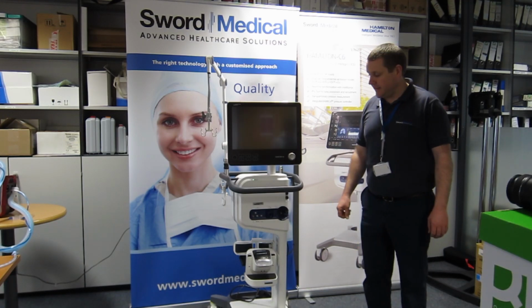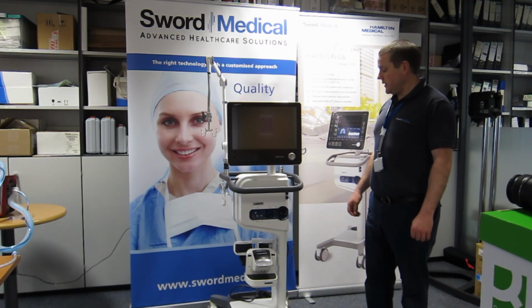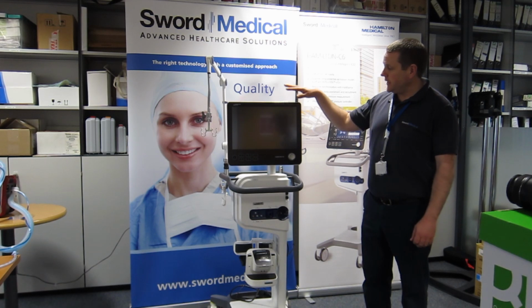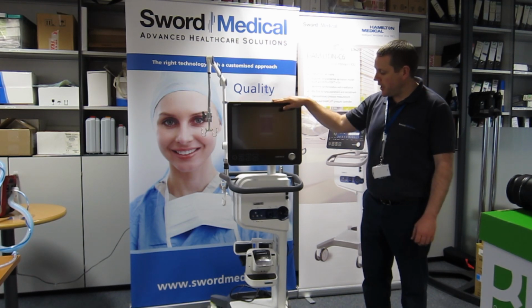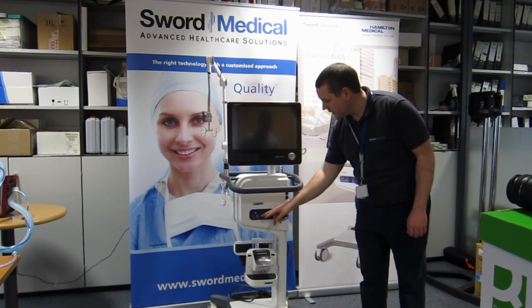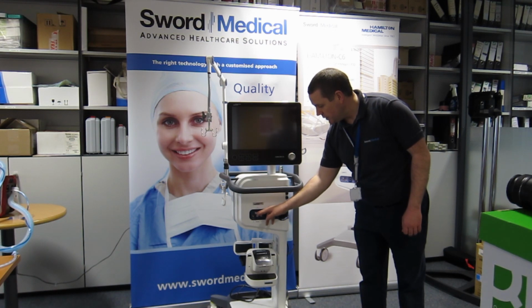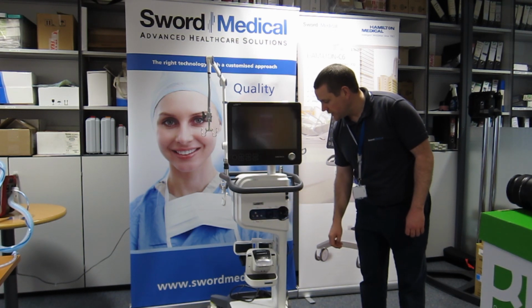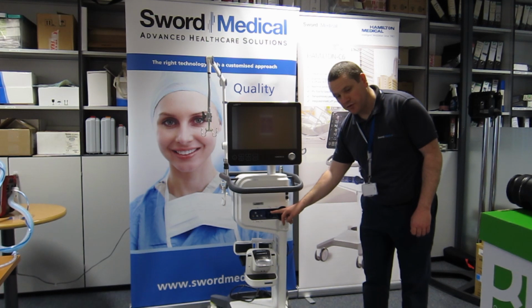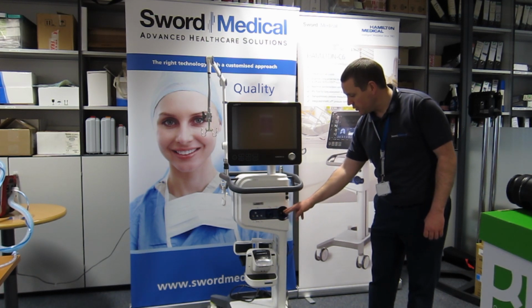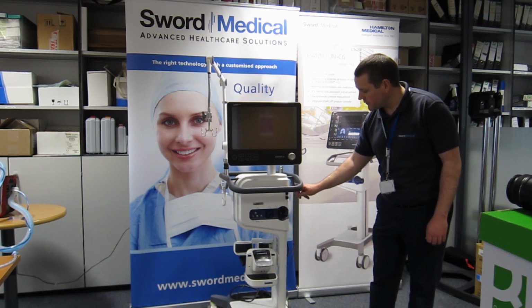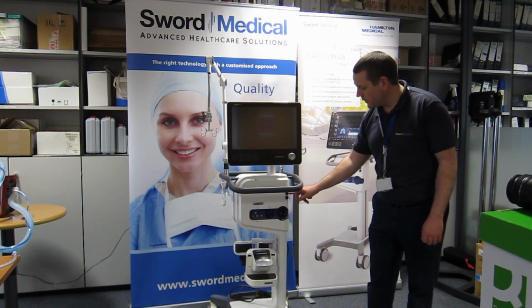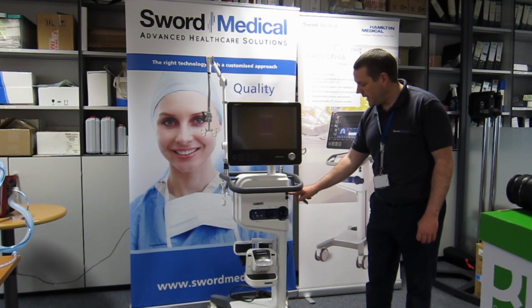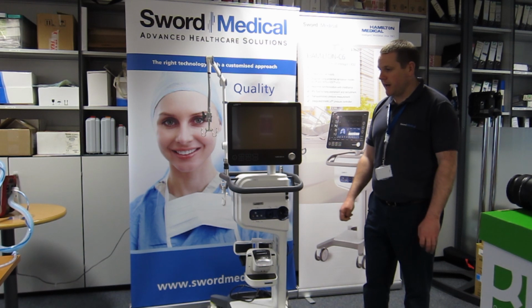Okay, so today we're going to look at the Hamilton C6 ventilator. Here is the ventilator unit itself, and here's the ventilator screen with the alarm bar on top. On the front of the vent you'll see ports, the blue and the silver port, and that's where the flow sensor is going to plug on. We've got our inspiratory port, and here we've got our expiratory port, and on the side here we've got ports for CO2 for capnography, but also a port for SpO2, and also where our Aerogen nebulizer is going to plug in.